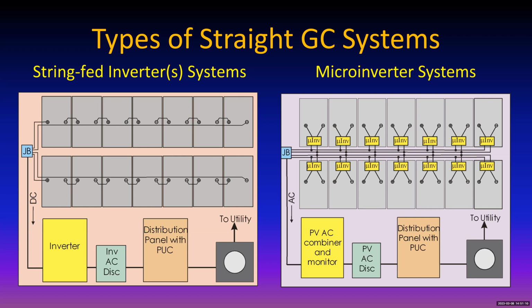So in the microinverter system here, you can see the DC goes into the microinverter, and the microinverter connects to two wires, line 1 and line 2, and the output of that microinverter is 240 volts AC. Now that's residential. It could be 208 if you got a 120/208 service, but typically the large majority of the systems are using 240 volts, and that's straight 240, not a split 120/240, but just 240 volts. But notice they're all connected to 240 volts. The output voltage of all of these inverters is essentially the same, except for a very small voltage drop in the wiring between them.